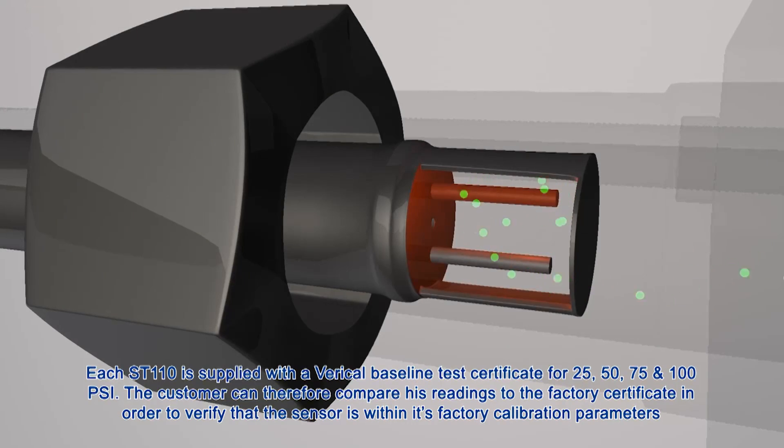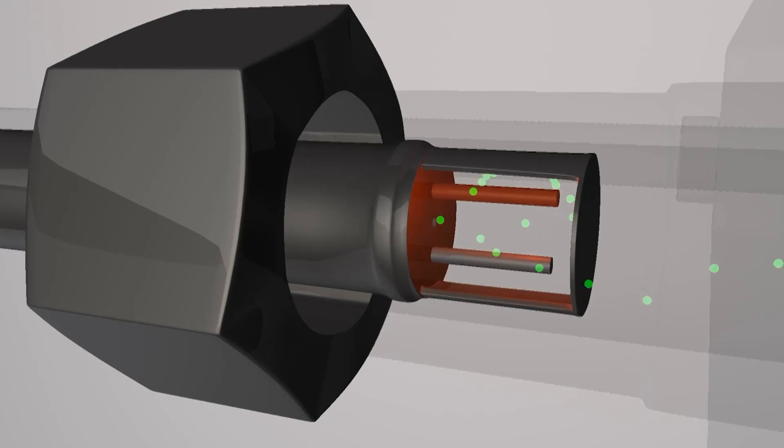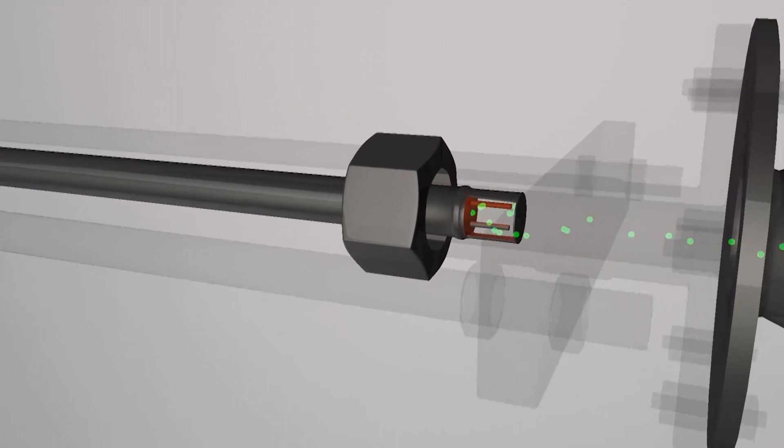Each ST110 is supplied with a Vari-Cal baseline test certificate for 25, 50, 75, and 100 PSI. The customer can therefore compare his readings to the factory certificate in order to verify that the sensor is within its factory calibration parameters.